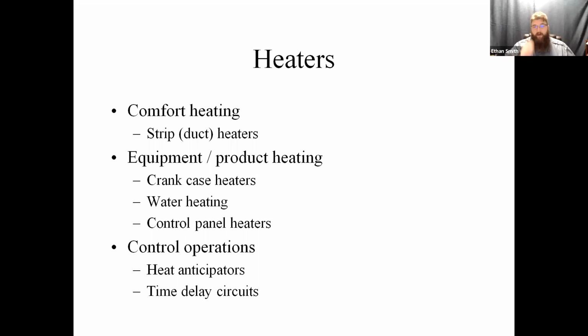So there's a component called, and it just left me, a heat sequencer that we see in electric heating sometimes. You'll have a single stage of electric heat, but you'll have 3 circuits, and a heat sequencer is basically just a little heat activated switch. When you send it the call for heat, it will energize the first circuit of electric heat, and then it'll heat itself internally. And once it heats itself internally enough, it closes another set of contacts and possibly a third set of contacts. They were called heat sequencers. Other places you'll see heaters, old slow open gas valves, guys. The slow open gas valves are a heated gas valve. And as that heater heats up, it allows that gas valve to open slowly versus a solenoid actuated gas valve, which opens instantaneously.